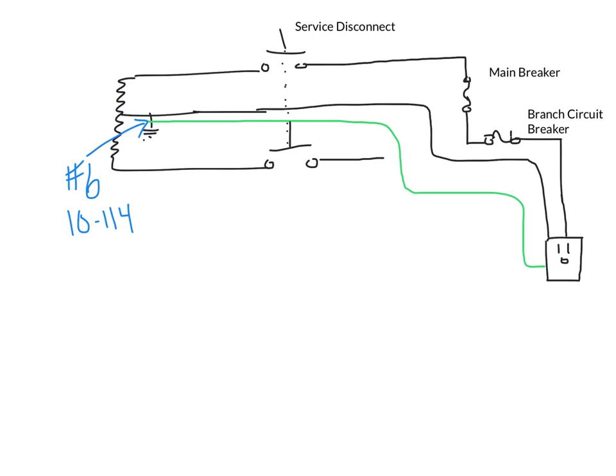This is why 10-114 tells us that our grounding conductor only has to be a number 6. The idea here is that that conductor is not actually carrying fault current. It's just providing a reference. From a theory standpoint, that conductor could be even smaller. It could be a number 14 because it doesn't actually carry any amount of current. The reason we use a number 6 is because that's the smallest size of conductor that we can bury in the earth without it being damaged by mechanical forces such as frost heave.